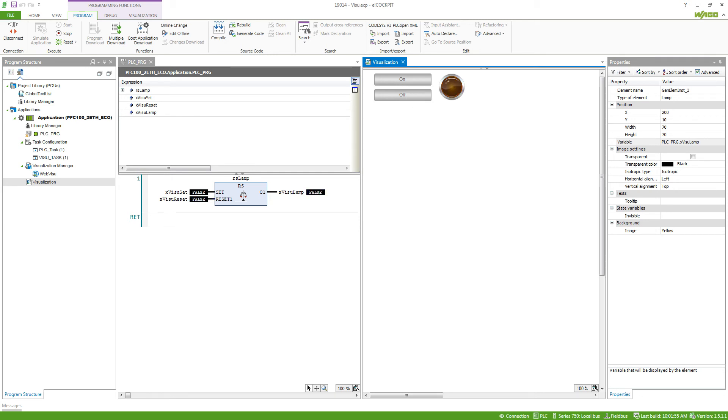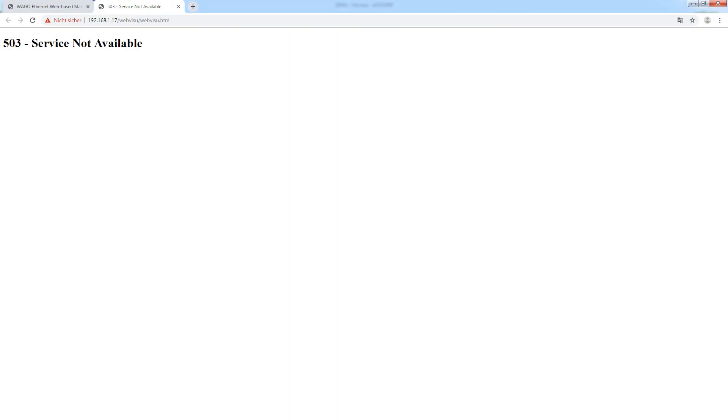Now we want to take a look at the visualization in the browser. To open the visualization in the browser you just type in the IP address slash webvisu. If you get the error 503 service not available, most likely your web server on the controller is not running.